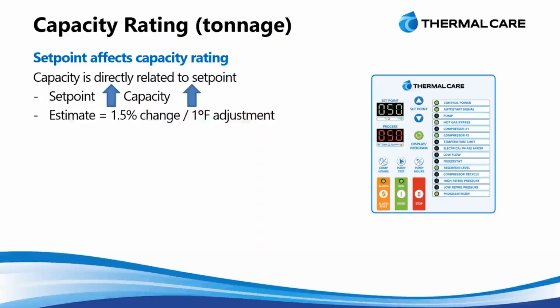And the first of those, and this is actually one of the most important, it's usually the first question I will ask when starting to design a system, is what is the temperature of the water required for the process? The reason for that is when I change away from that nominal 50-degree set point, I will start to change the capacity of the unit. So if we look over here, in the set point demonstrated here, we have a nominal 10-ton chiller that we're using as our example. As we increase that set point, we gain a percentage of capacity with each one. As we continue up here, we'll get almost an additional whole extra ton of cooling by raising that set point temperature by 5 degrees.